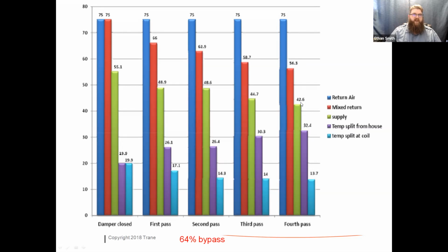It's going to cycle off for 5 minutes probably if it's a traditional zoning system. It'll cycle back on and start cooling, the 4th pass rolls around again, and we're going to cycle off again. I actually worked on a zoning system that unfortunately my company installed that operated just like this. That thing had more off time than it had operating time. It took 3.5 minutes to trip the discharge air temperature sensor, and it had a 5-minute off cycle. Needless to say, the 2nd floor was very warm.